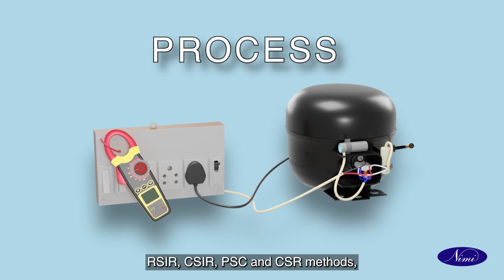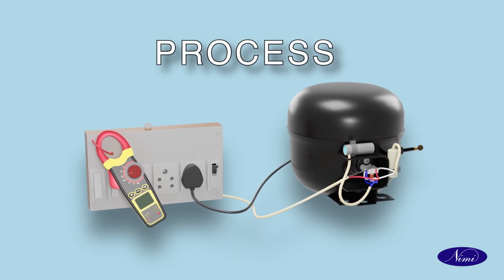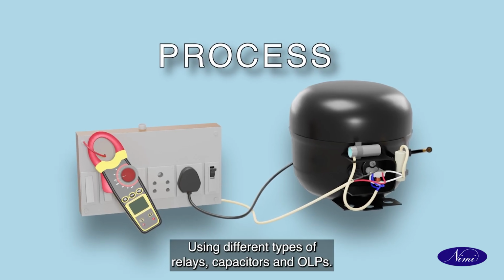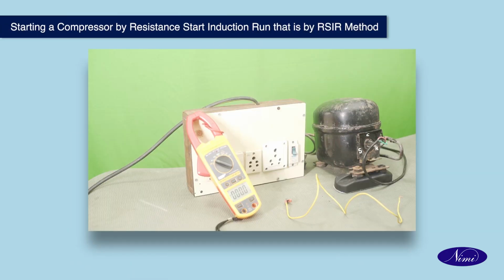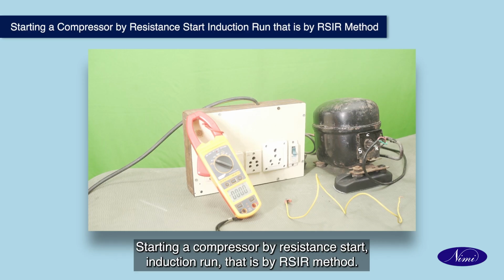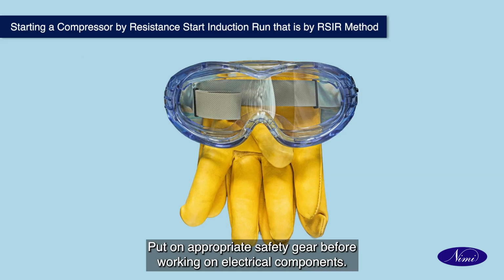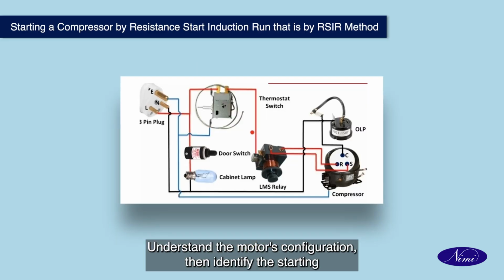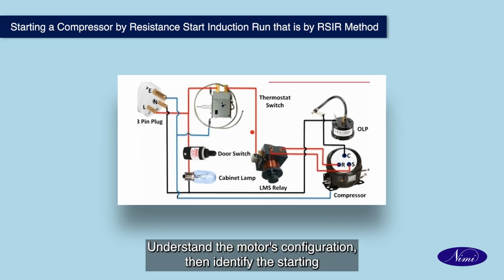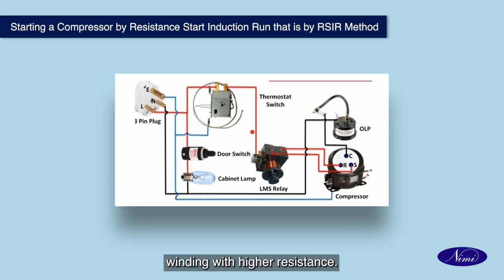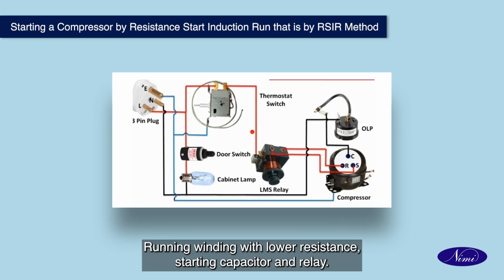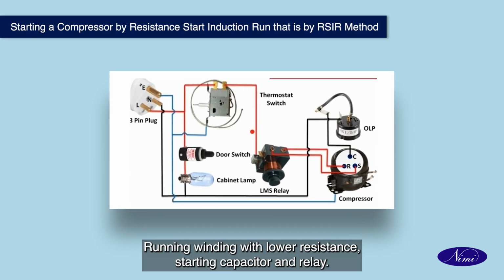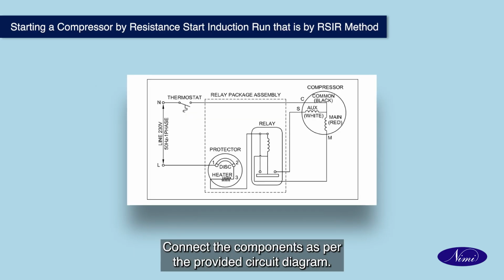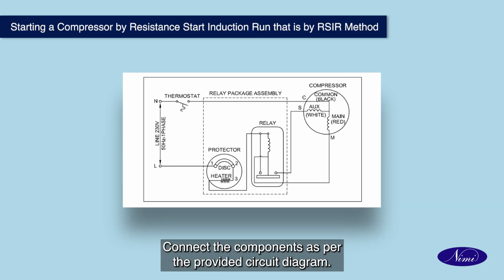CSIR, PSC and CSR methods using different types of relays, capacitors and OLPs. Starting a compressor by resistance start induction run, that is by RSIR method. Put on appropriate safety gear before working on electrical components. Understand the motor's configuration, then identify the starting winding with higher resistance, running winding with lower resistance, starting capacitor and relay. Connect the components as per the provided circuit diagram.